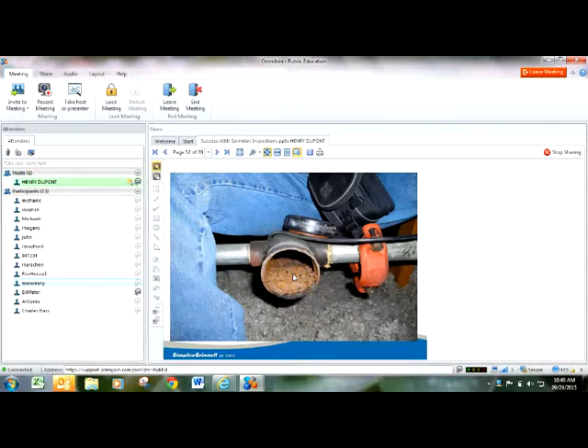So you can imagine, if you've got a sprinkler head with a 1/2-inch orifice way out at the end of a branch line, and it goes off, you're moving all this water and whatever that stuff is growing inside the sprinkler system through that 1.25-inch branch line, which reduces down to 1 inch and is trying to come out a 1/2-inch orifice. You can imagine how much water you're going to get out of your sprinkler system, and that fire is going to continue to grow, and the sprinkler system's not going to be able to keep up with it.